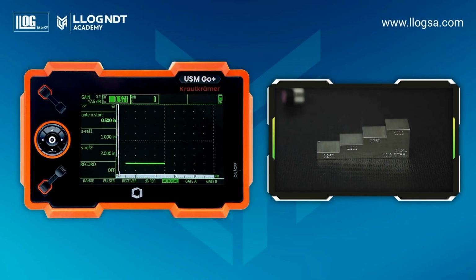It is time to perform the straight beam calibration using 2 known references, with a step block and a 5 MHz transducer. We begin by entering the Auto Calibration function menu. For reference 1, using the lower keys, we enter the value of the smaller thickness. In this example, 1/2 inch. For reference 2, we enter the value of the larger thickness, 1 inch. For fine adjustment of these values, use the left or right navigation keys.